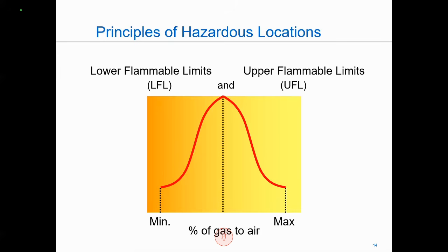Now, depending on the particular substance, those upper and lower flammable limits change. So, for example, acetone is 2.5 to 13%, as compared to acetylene, which is 2.5 to 100%. So again, depending on the particular substance, those levels change. And those are the levels that are printed by NFPA, but there are some other factors that can possibly change the upper and lower flammable limits. If you had an area that was extremely hot or with extreme pressure, in that particular case, the flammable limits could open up slightly. Or if you had an area that was exceptionally cold, the upper and lower flammable limits could close in slightly.